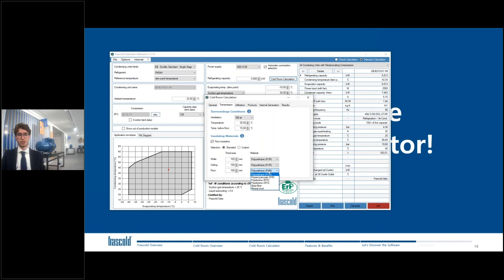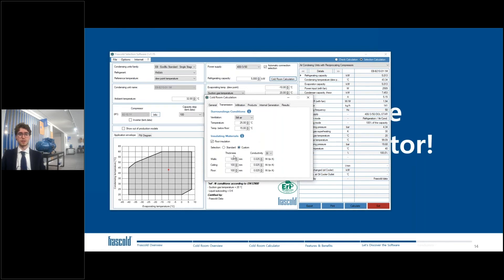Regarding the floor, a note about glass fiber and mineral wool: you can select these insulating materials, but in the specific case of the floor, they have no structural strength, so it is better to choose other materials — this will be clarified in the next software release. The custom selection also allows setting different thicknesses for walls, ceiling, and floor, and then specifying the thermal conductivity value of the insulating material. The default shown is a typical value for polyurethane, but you can select different values and also choose different units — IP or SI.